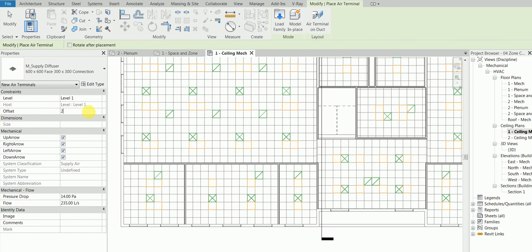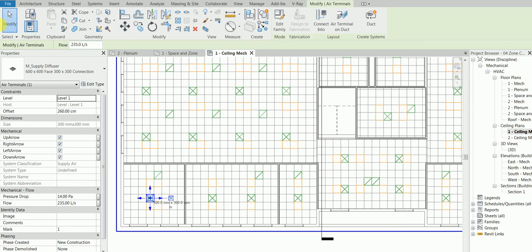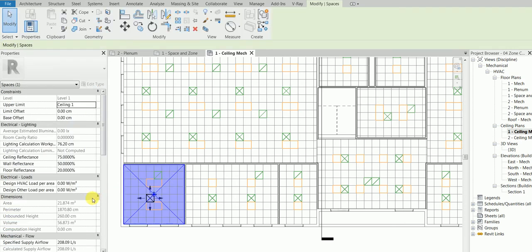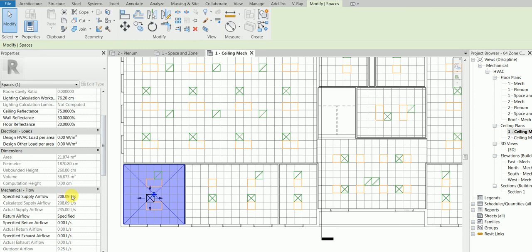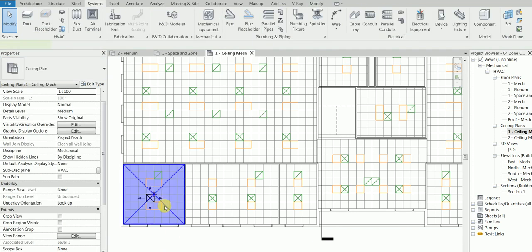Now let's say we place one air terminal in this space. The offset is 260. If we check the space properties, the required airflow is 208 liters per second, but the air terminal is set to 235. We need to adjust it to something like 210 — very close, within the three to five percent maximum tolerance. Once we set it to 210 and click Actual Flow, it updates accordingly.